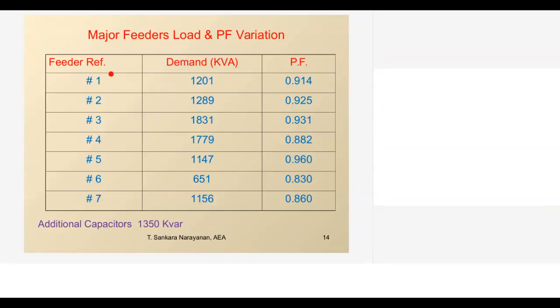So for this plant, again, for the different feeders, what is the demand, what is the existing power factor? If APFC is already there, why is there so much variation in power factor? All panels should maintain 0.95 because APFC is set for 0.95. So when these variations are monitored, then we can see whether there is a failure in capacitors, or at certain places they require an additional capacitor bank. So the additional capacitors required are estimated at around 1350 kVAr.